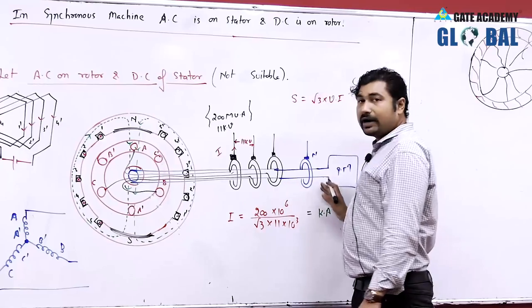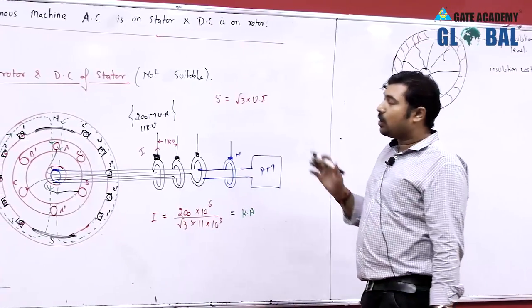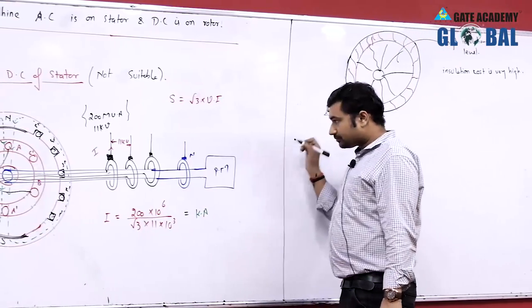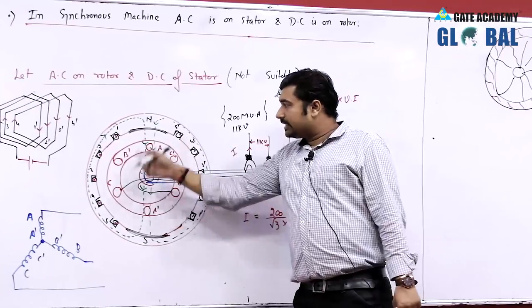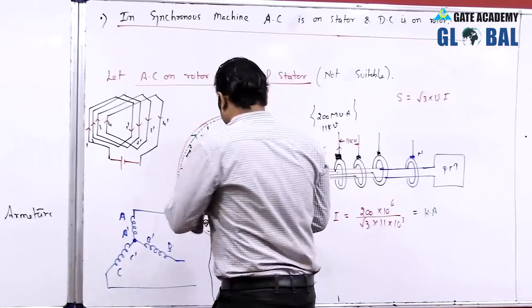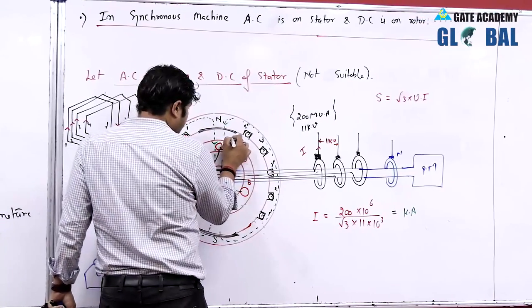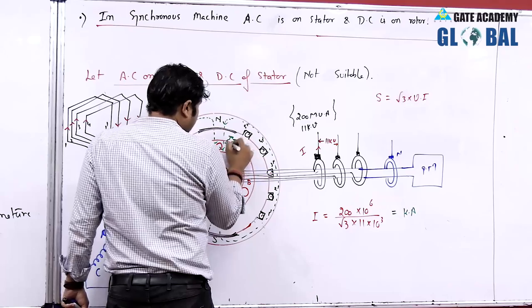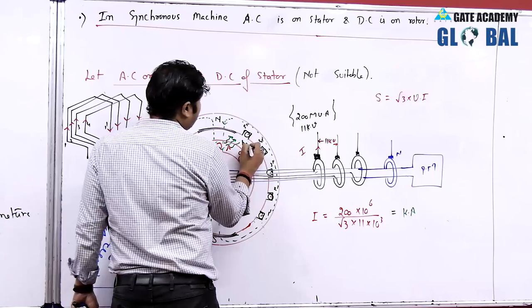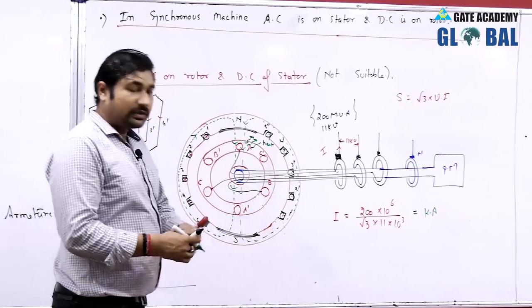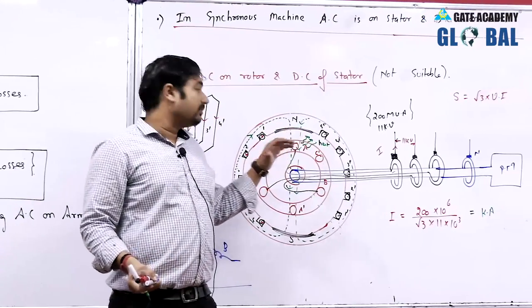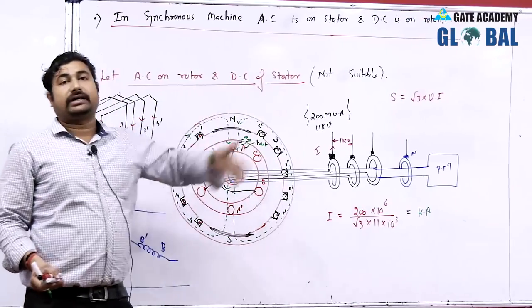Problem 1: Very high centrifugal force acts on the conductor due to large rotor conductor weight. Problem 2: Four slip rings are required with high insulation cost and large size, increasing overall machine cost. Problem 3: Effective hydrogen cooling is not possible if AC is on the rotor. Kilo-ampere currents flowing in the rotor wire produce I²R loss in the form of heat, which must be removed or the machine gets damaged.